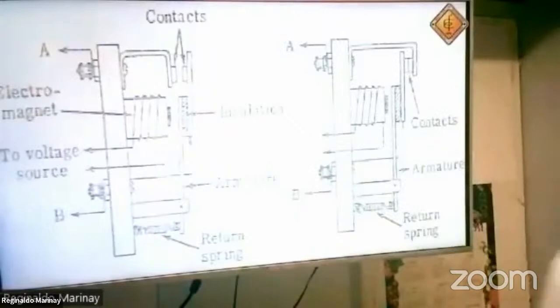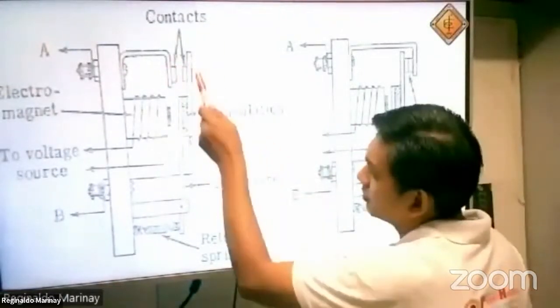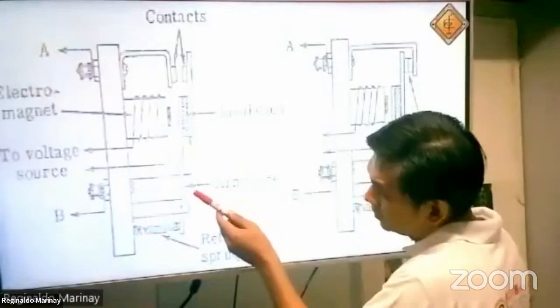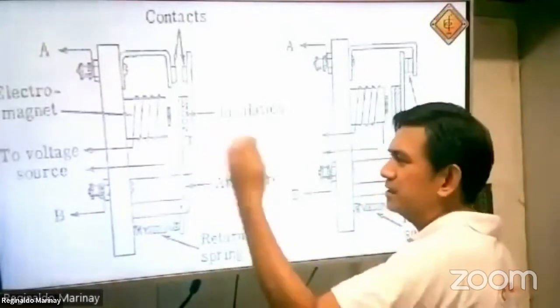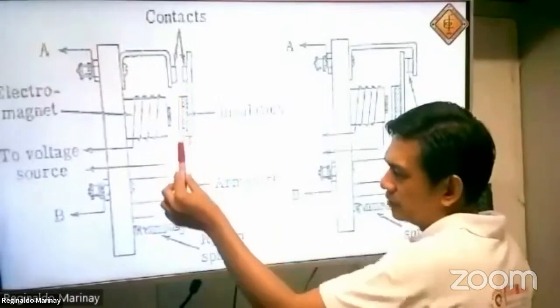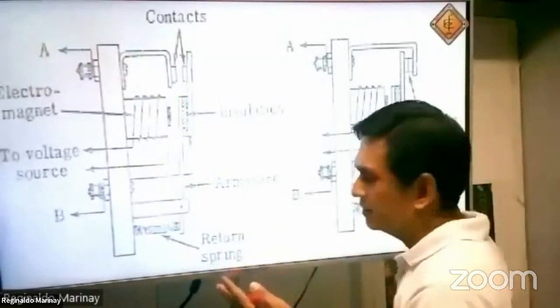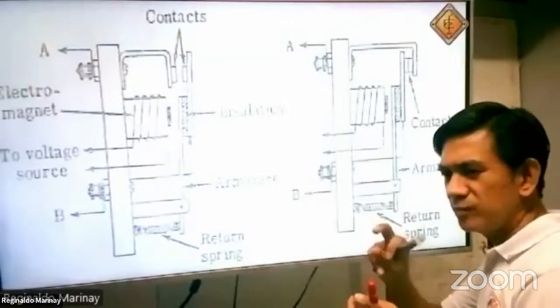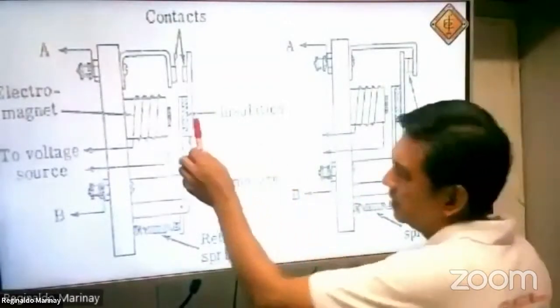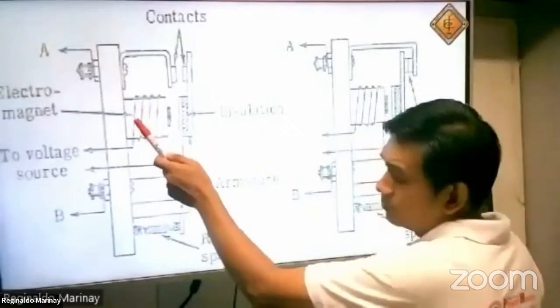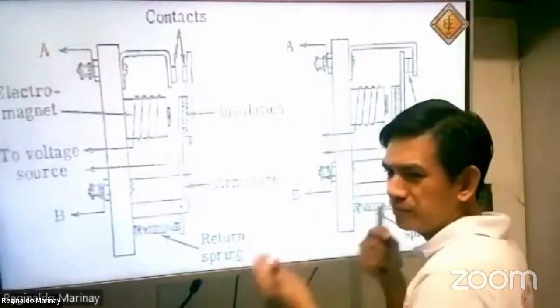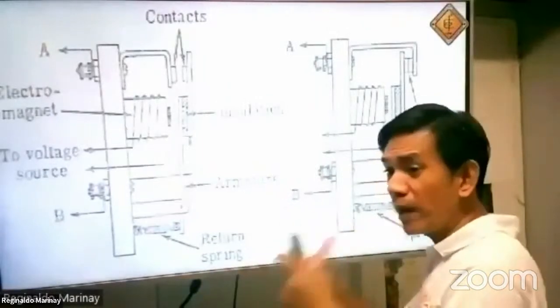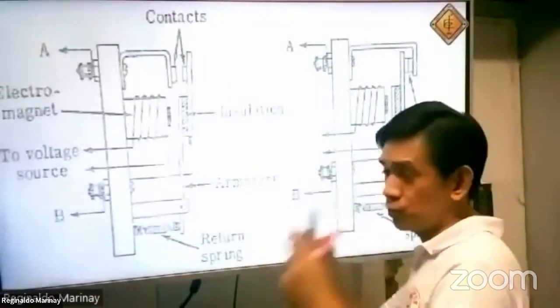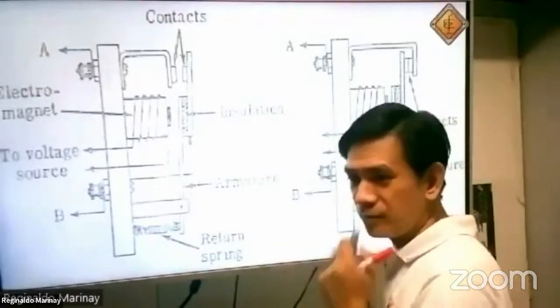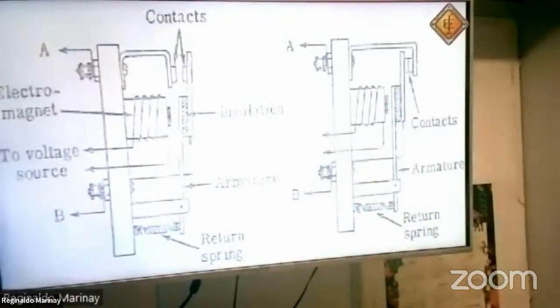You will see here that this is a normally open contact. You see there is an armature. Basically, if we mean an armature for the magnetic contactor, even in the machineries, right? If we mean armature, it is a moving part. Take a look here. This is the electromagnet or the coil. An iron core plus the winding or the coil is equal to electromagnet. Remember that.